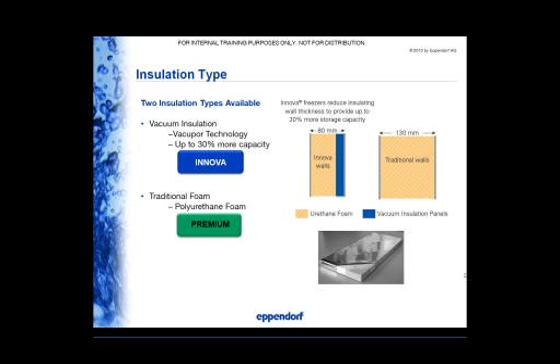So insulation type, this really ties into location of the freezer because of the amount of extra space that you will gain by utilizing vacuum insulation paneling. But I also wanted to state that not all vacuum insulation panelings are created equal. New Brunswick, we offer vacuum insulation paneling using Vacupor technology. Vacupor technology, this is the reason why New Brunswick can offer a 12-year warranty on vacuum insulation paneling. But again, freezers equipped with vacuum insulation paneling will typically cost more. But in trade-off, you will get up to 30% more internal capacity on the same footprint.